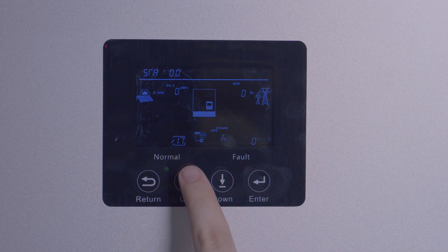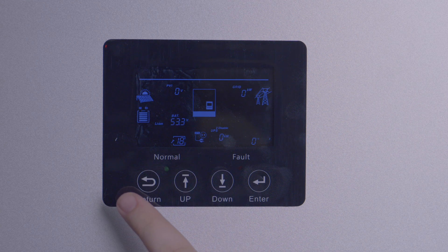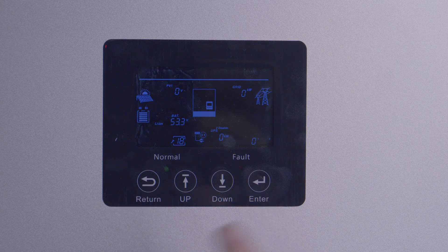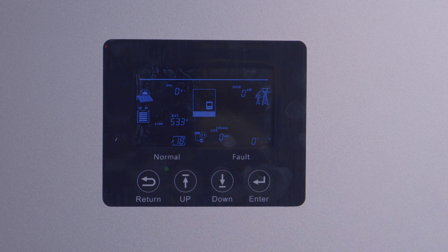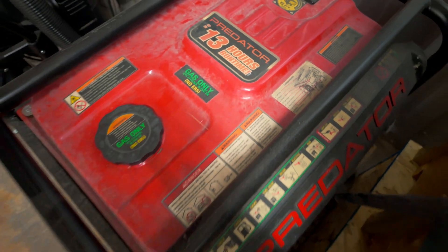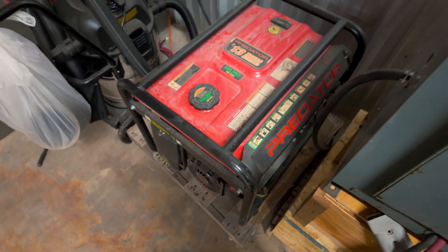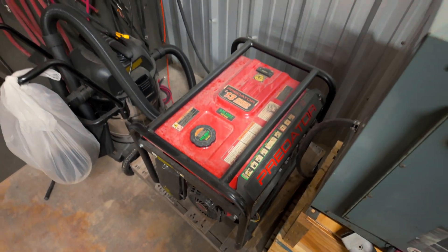Setting eighteen is max generator power. This is the limit at which your inverter will stop charging batteries from the generator, and if you have gen boost enabled, will discharge to compensate power to loads. It's best to set this to your generator's recommended continuous use for maximum fuel efficiency and sine wave quality.